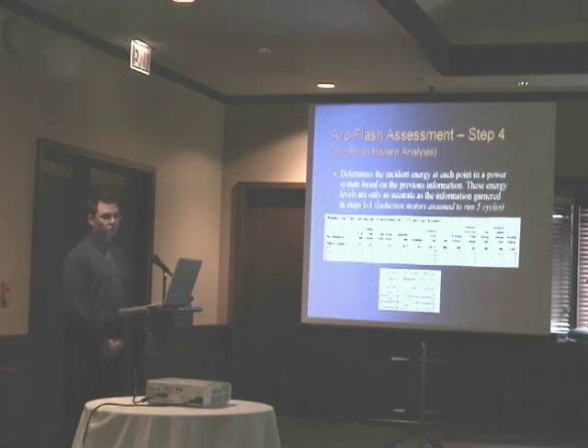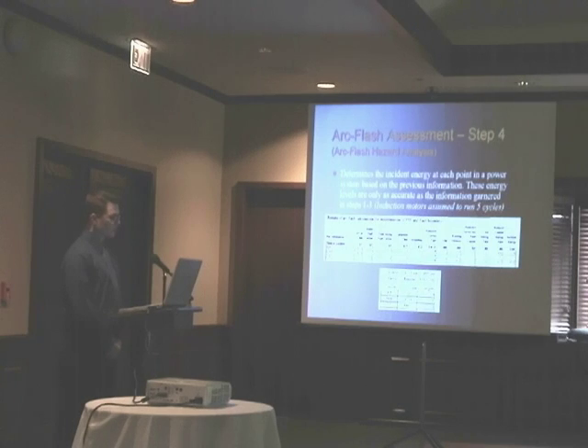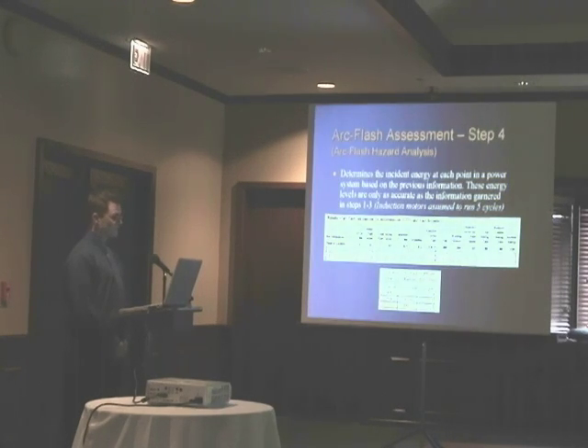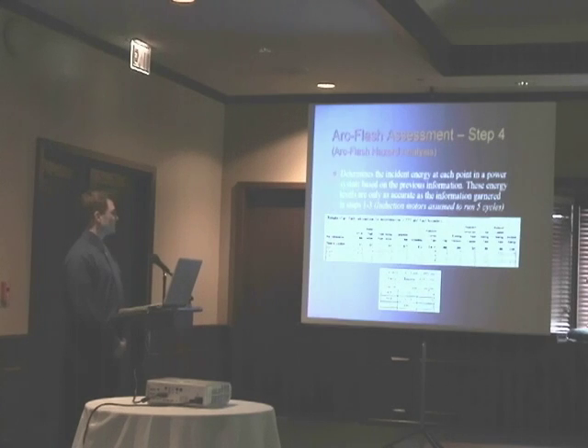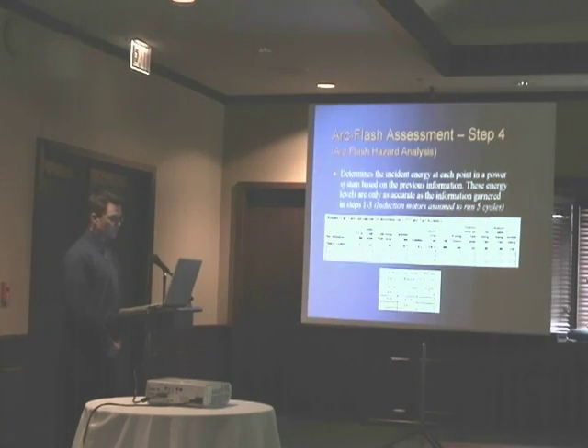After we get all the short circuit and protected device information, we go to step 4, which is an arc flash hazard analysis. This determines the incident energy at each point in the power system based on the previous information. These energy levels are only as accurate as the information gathered through the first 3 steps.